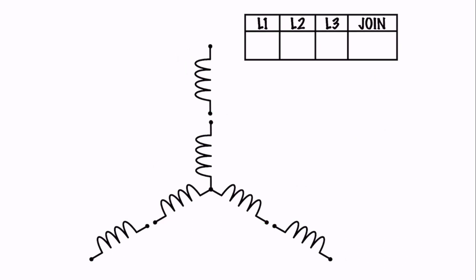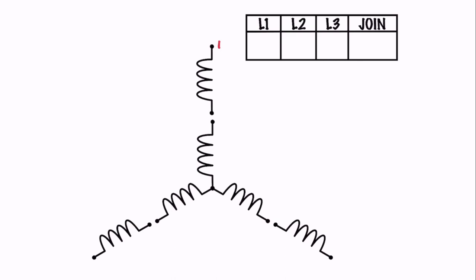The next one — the higher voltage connection — is super easy. Higher voltages in series add together. If each one of these windings is rated for 230 volts, then 230 plus 230 gives us 460. We number the leads the same way, and we just connect them in series. So we go boop, boop, boop — those are connected. Then we connect our line one, line two, and line three.